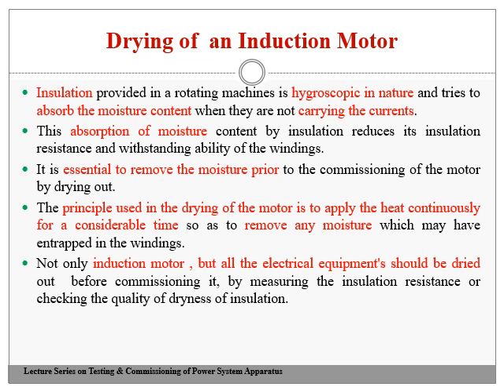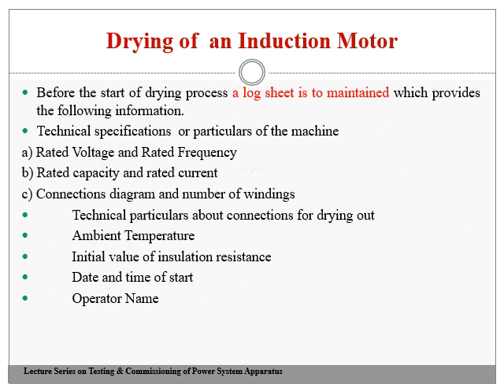We'll see that one. Next, we'll go to the next part. Before the start of a drying process, a log sheet is maintained. I cannot carry out the drying process whenever I like. First, I have to check the insulation resistance. Then, if it is less than the permissible limit specified by the standards, I need a drying process. The method has to be selected depending upon the capacity of the induction motor.